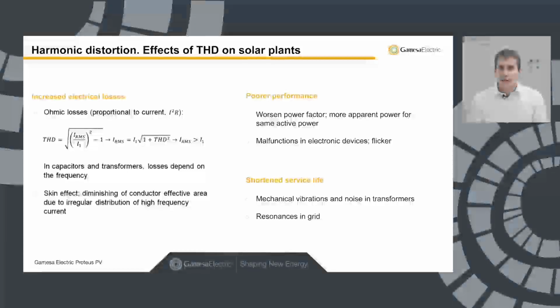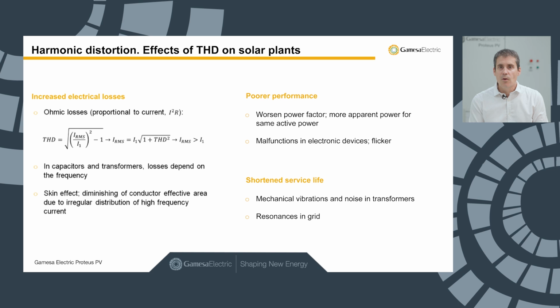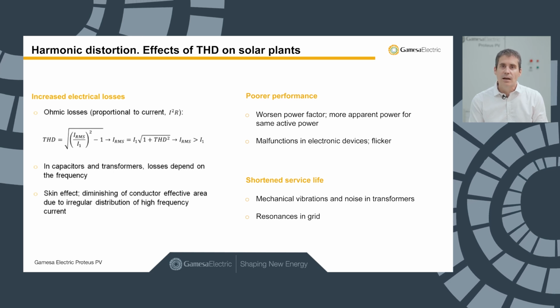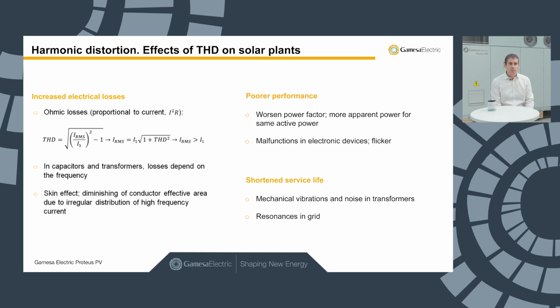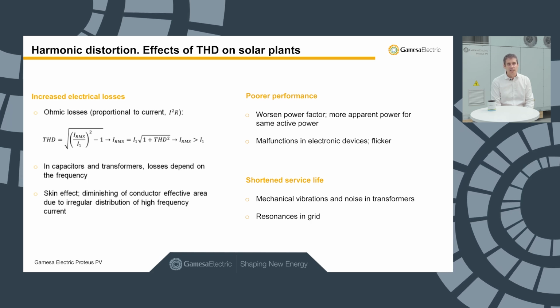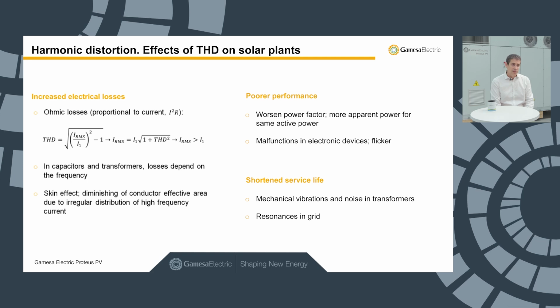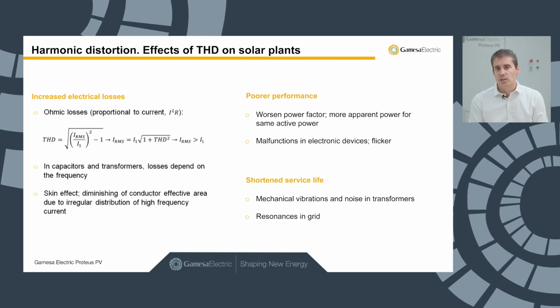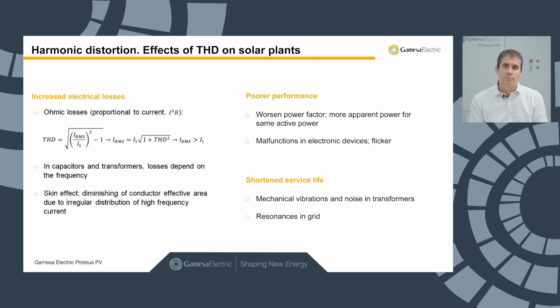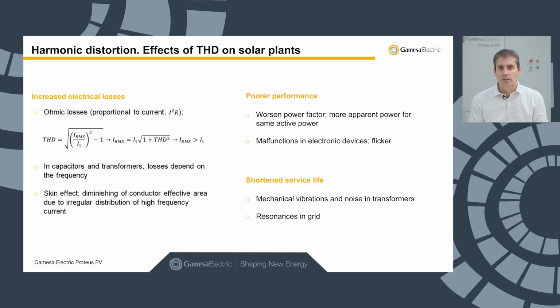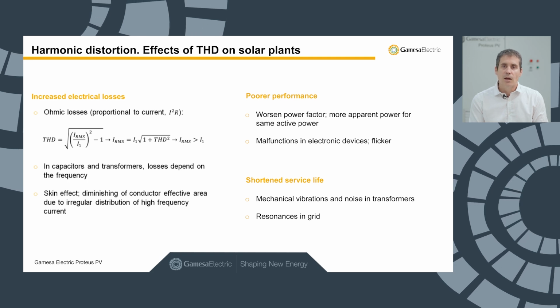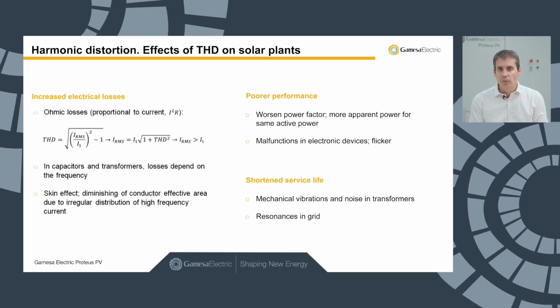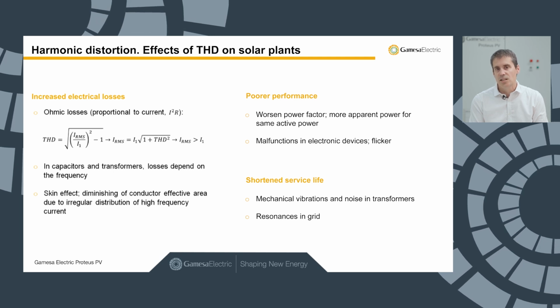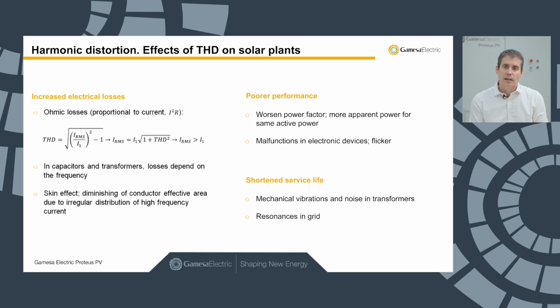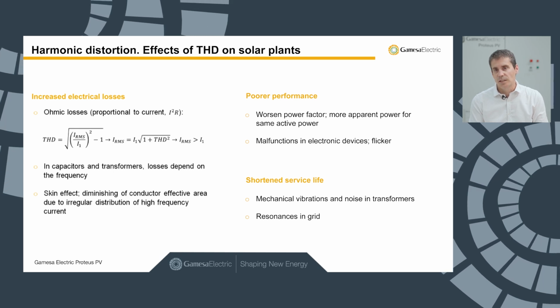The second key effect is poorer performance of the solar plant. A high THD will worsen the power factor, and we will need more apparent power for the same active power. Also, malfunction in electronic devices is likely to happen due to flicker. The third problem is the shortened life of the transformers. Transformers are big equipment inside the solar power plant, and they will suffer mechanical vibration beyond their limits because of this high THD, and resonance in the grid can also occur because of THD.